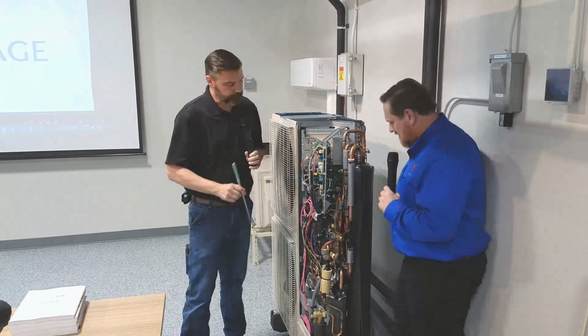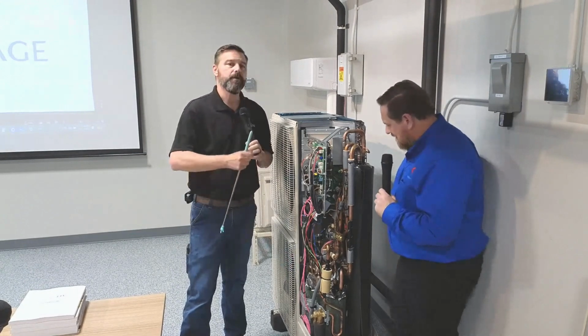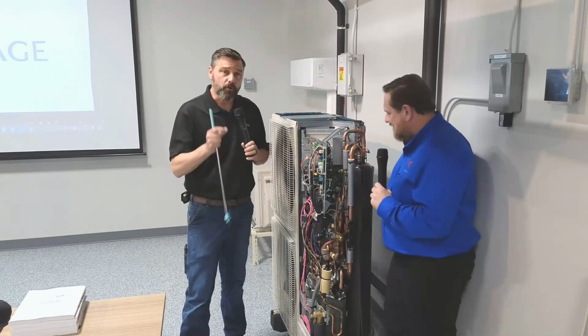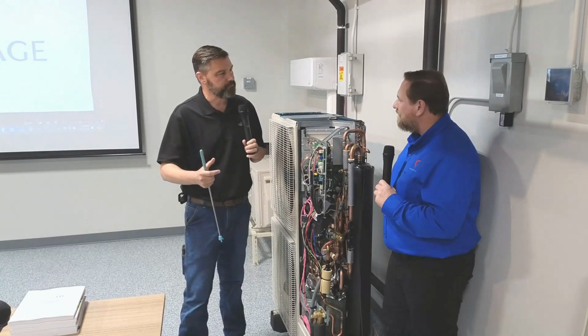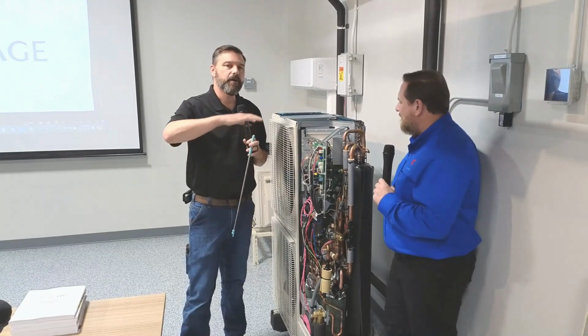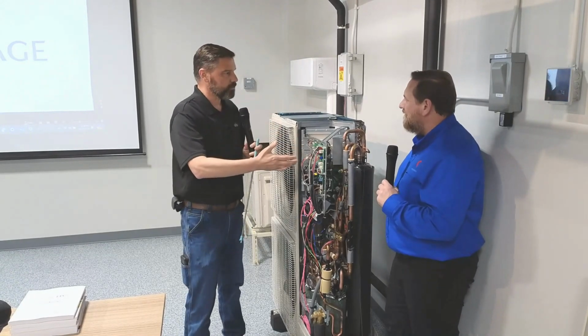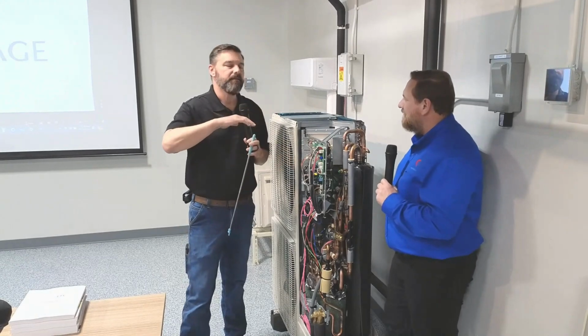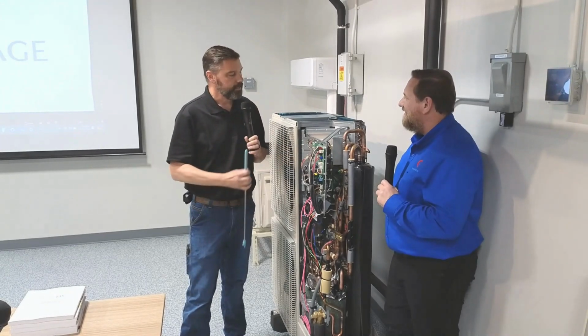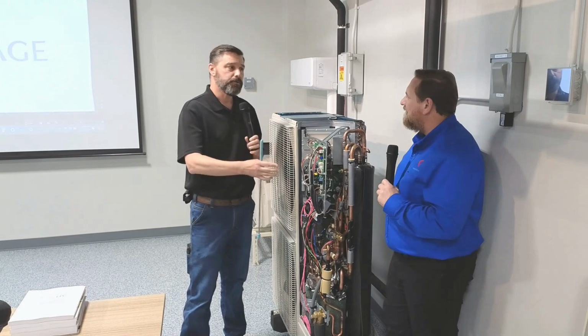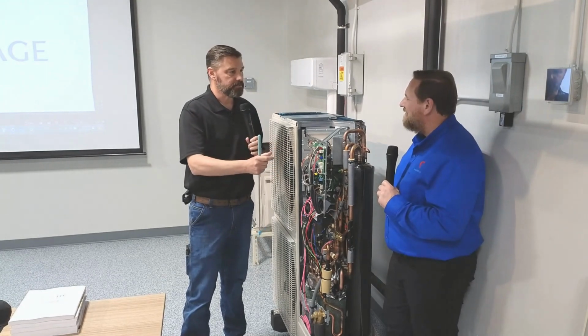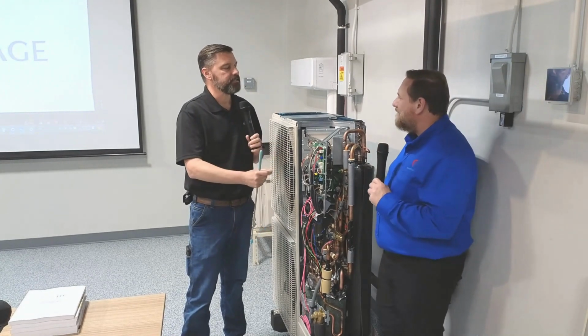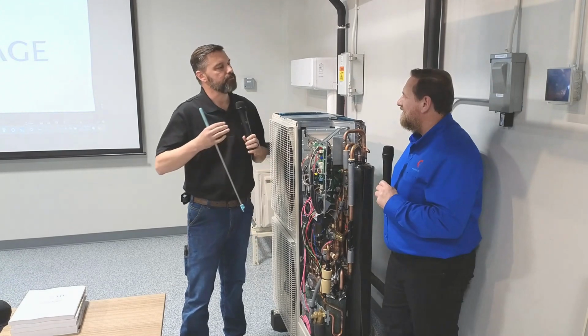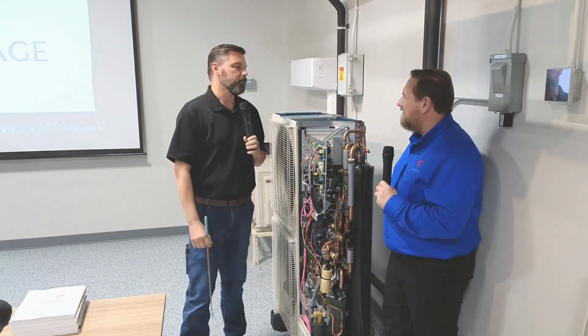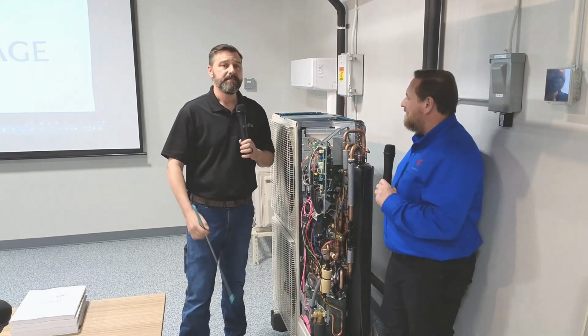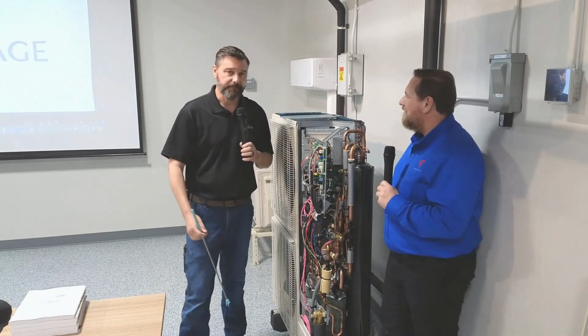With newer inverter-driven compressors and the ability to monitor and control refrigerant flow through an electronic expansion valve, compressors now operate very smoothly, almost like cruise control in a car, maintaining steady-state heat output. Because of that -15 rating, if you do your load calc, we can design the system to meet your demands at that design temperature, and the compressor just ramps down on milder days. So we can heat houses down to very cold temperatures safely.